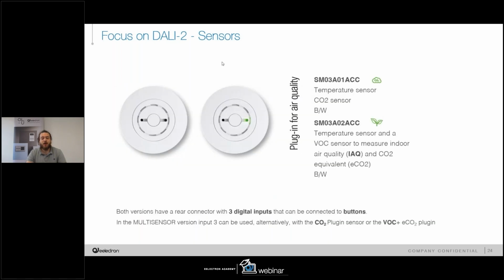Also, in the DALI version, you can wire our smart probe. This means that we can read the ambient CO2 value or the VOC value plus the equivalent CO2, depending on the model. With the first one, we have a more precise measurement of the CO2 since there is a CO2 probe inside the device. With the second one, we will have a more complete control of the indoor air quality index, where we have the VOC, that are the volatile organic compounds present in the air, and also the equivalent CO2. Equivalent because we estimate a CO2 level depending on the other values that we receive from the probes. Remember that both sensors have 3 digital inputs on the back of the device, and only in the multi-sensor version can we wire the smart probes.